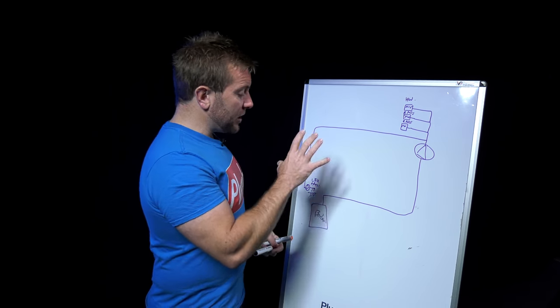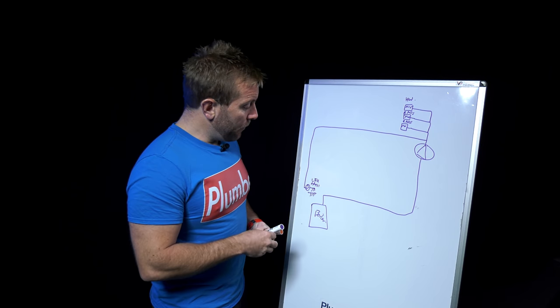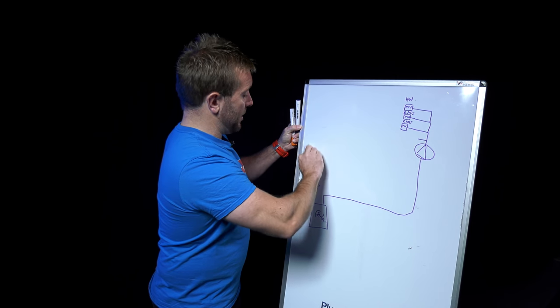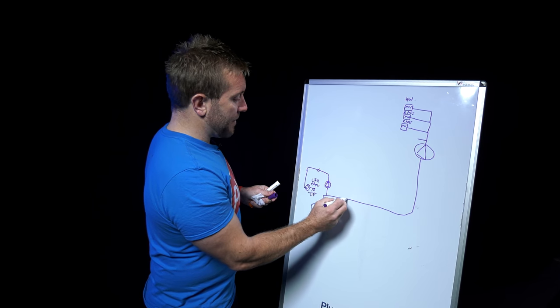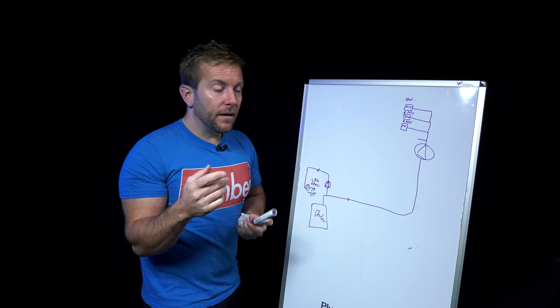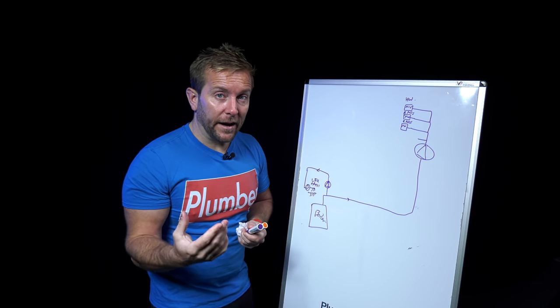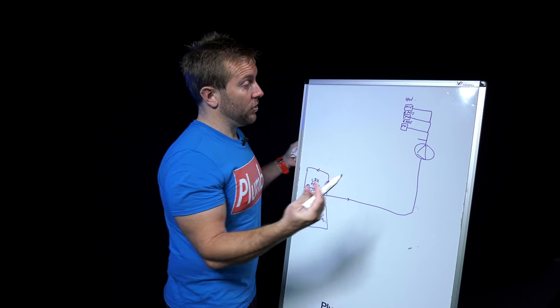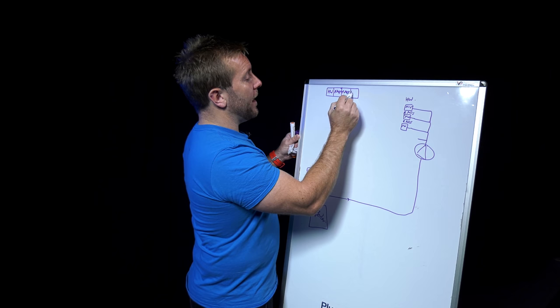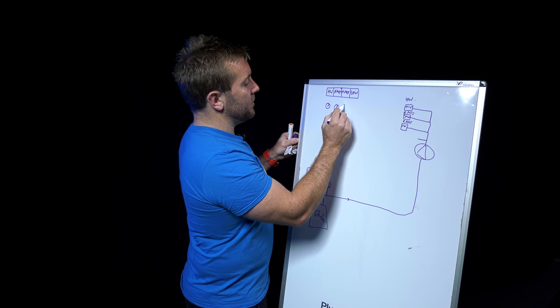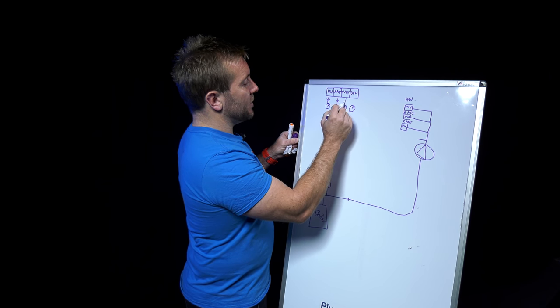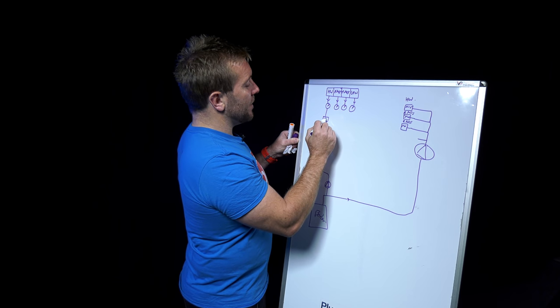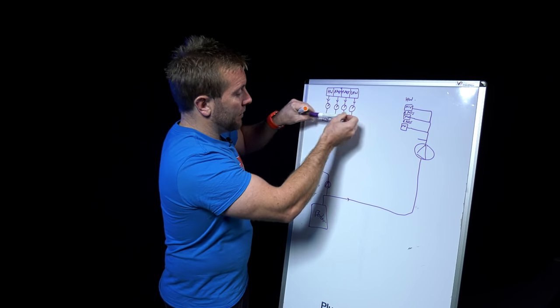This system wasn't working very well because we had a massive problem with the physical properties of flow going around the system. We were having this huge issue that we just weren't getting any flow here. The obvious solution, because these two were so near to each other, was to get rid of this bit. Why don't we just tee off the top of the boiler, put a little pump there, and then we can feed into that manifold. And also there were a couple of radiators around there that weren't getting hot. So let's use the knowledge that we gained earlier on and draw this whole system out in an electrical way.